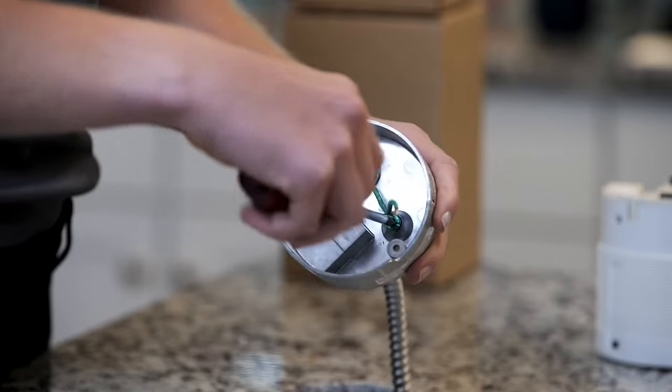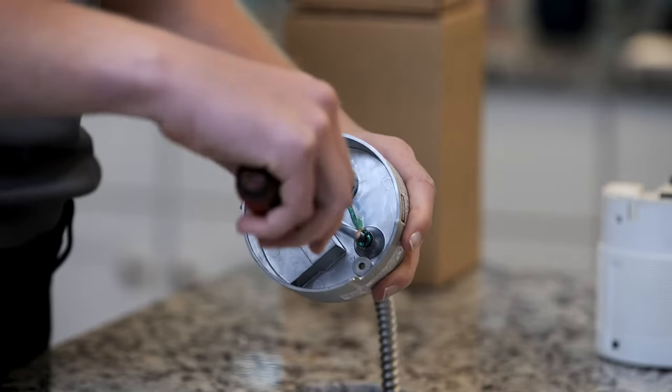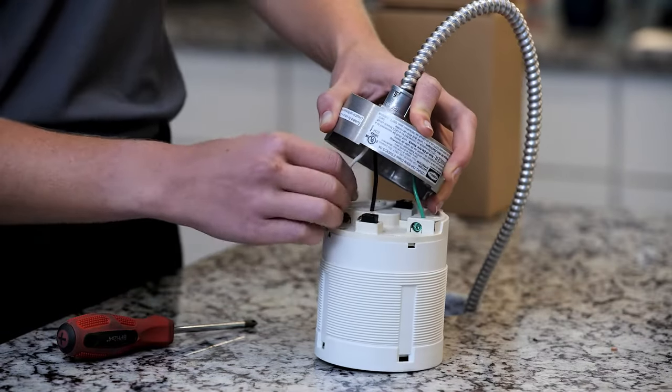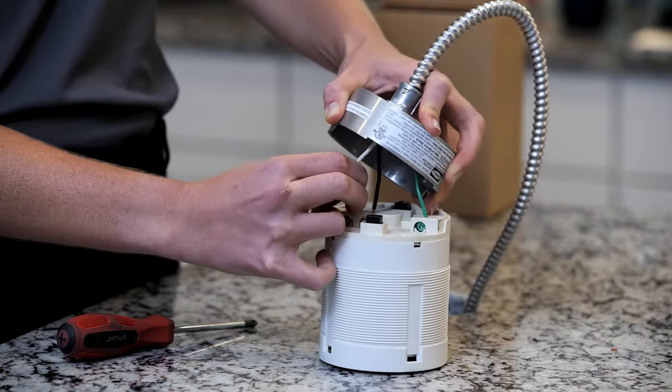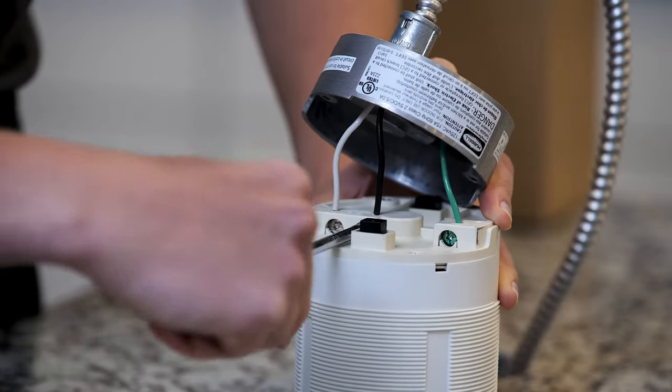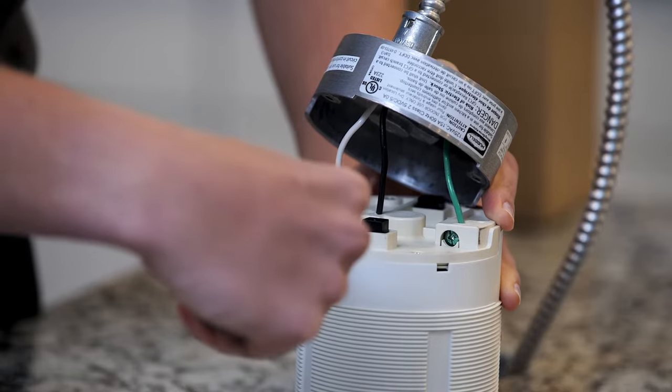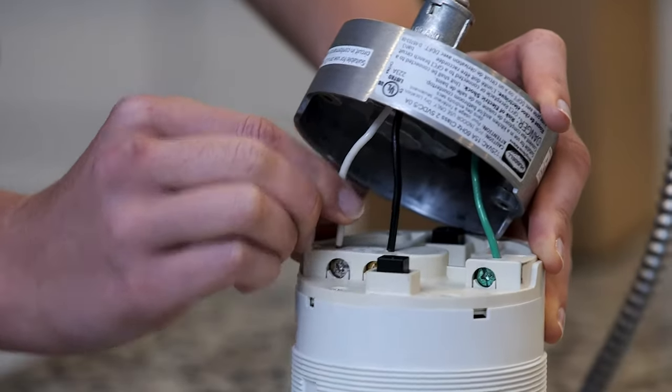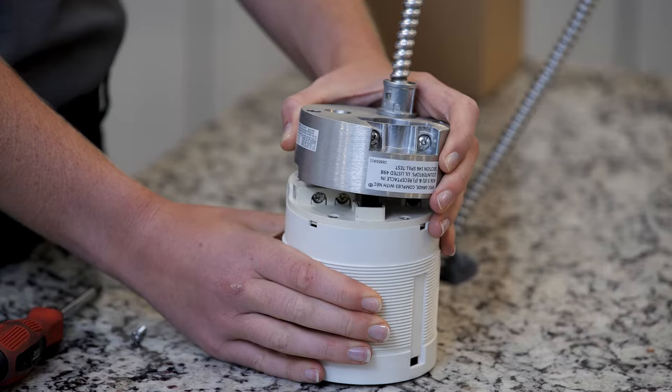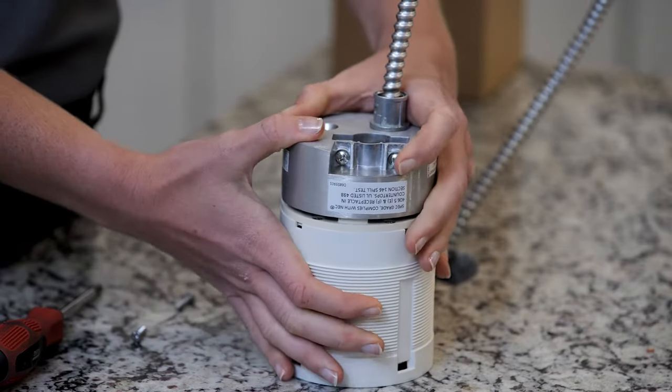Ground the base by bonding the green or bare wire to the green grounding screw. Terminate the white or gray wire to the white screw marked white and black or red wire to the brass screw marked hot. Reattach the base to the housing and secure with screws.